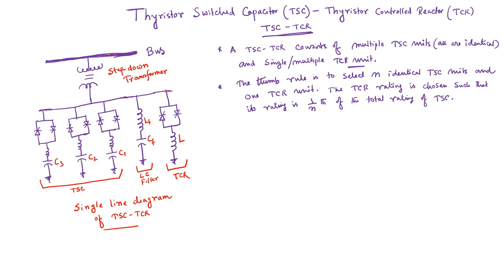So basically, as I said, the number of TCR units is kept less, usually a single or maximum 2, so that the total harmonic generation of the whole unit is less. Now, here what we will do is design a TSC-TCR so that we can understand its basic operating characteristics, that is voltage-current characteristics, very well.